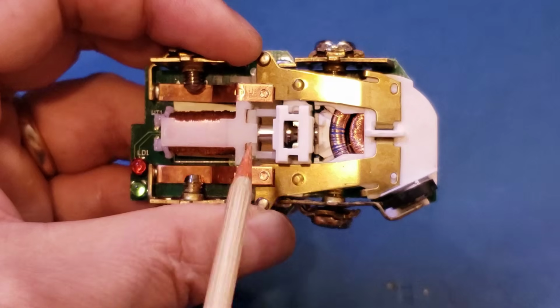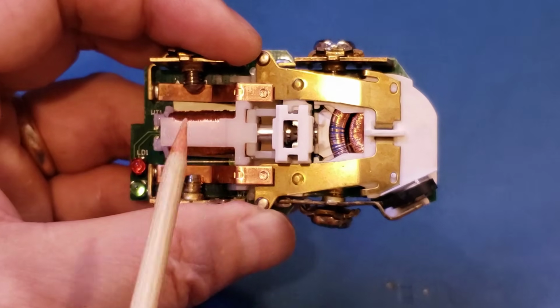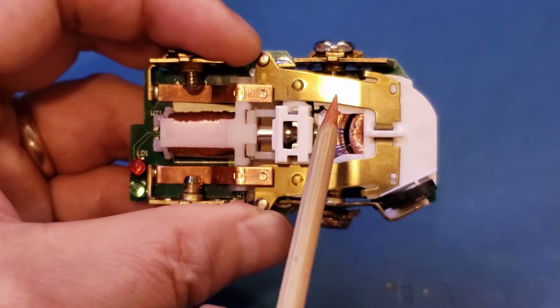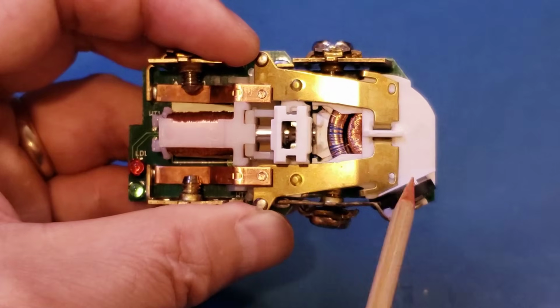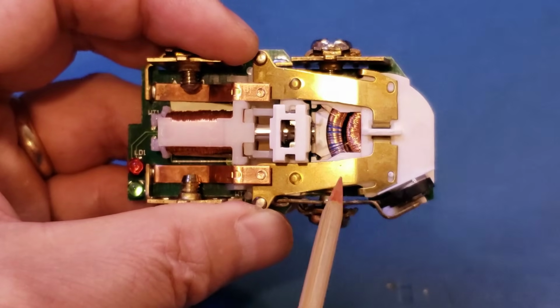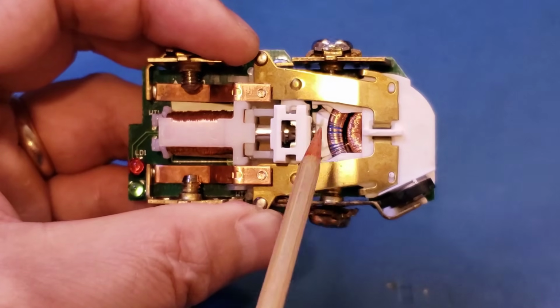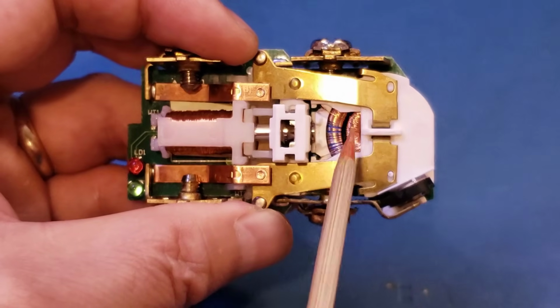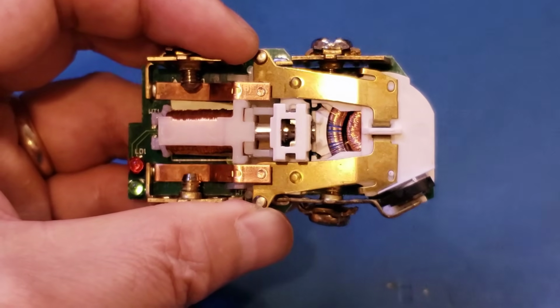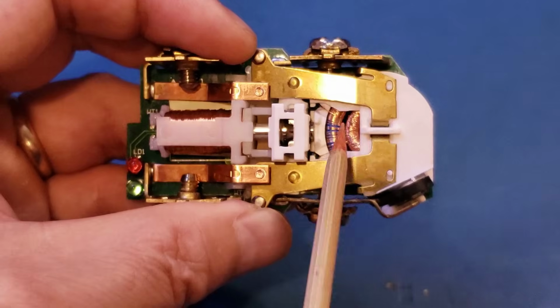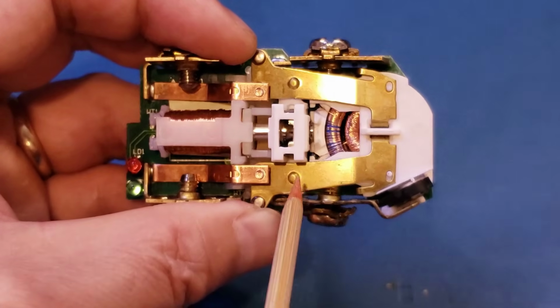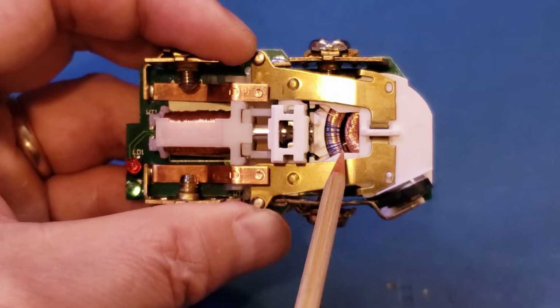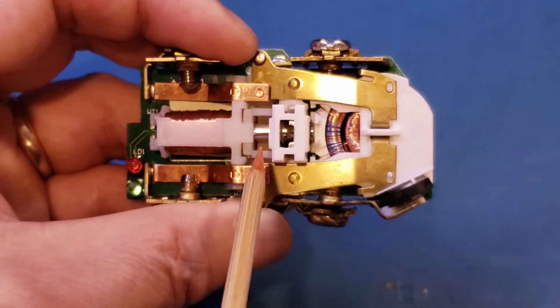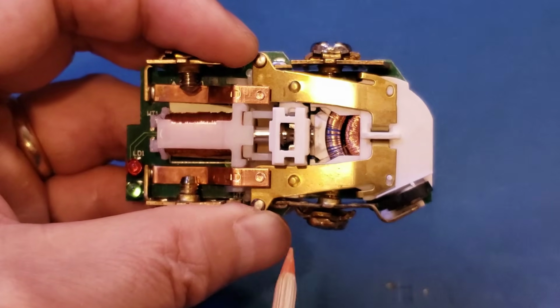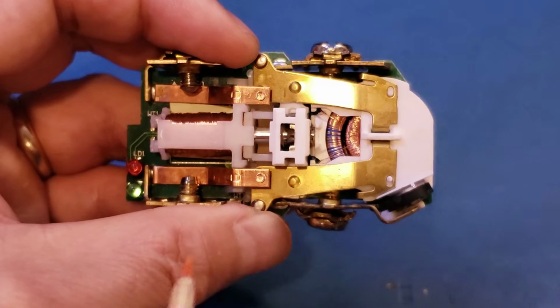In a ground fault situation, some of the current goes through a separate path into the ground directly, and that is actually outside the circuit here. So the current flowing through the live and neutral would be ever so slightly different, for example, a few milliamps. And that difference is being picked up by the sensing coil right here, and the GFCI circuitry would trip the solenoid relay and thus disconnect the live circuitry. So that's in general how ground fault detection works.